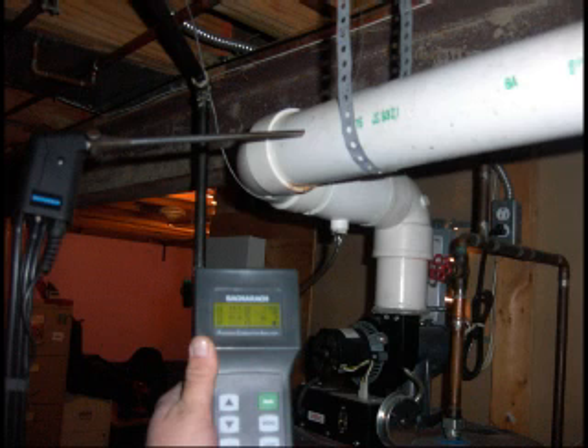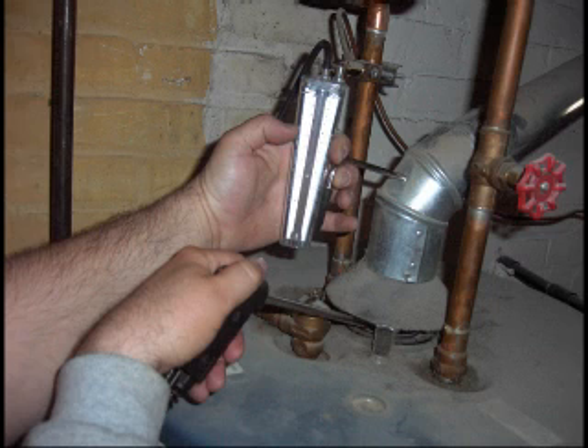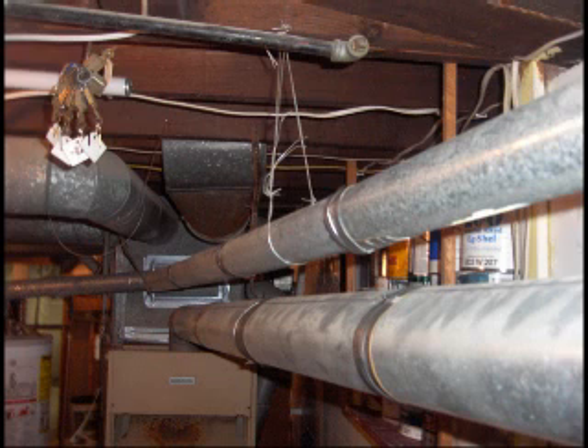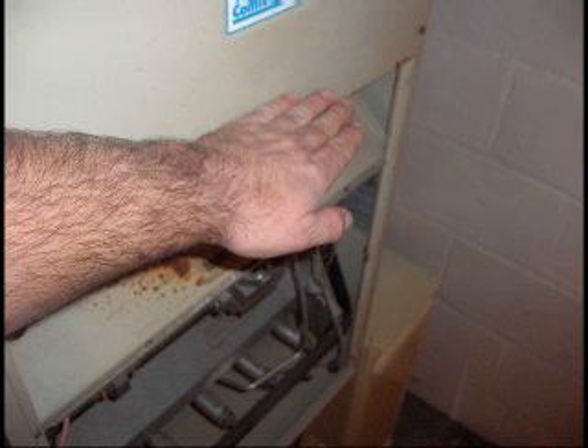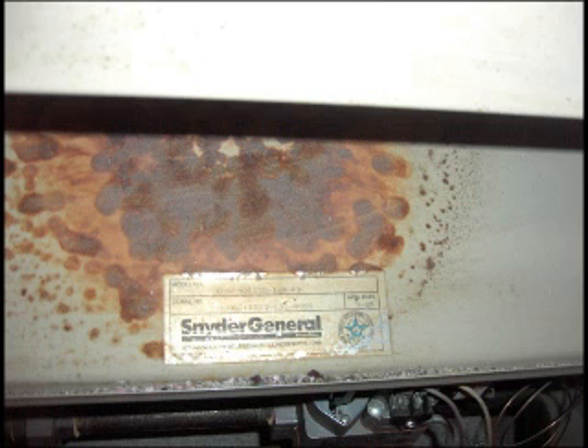You could have a venting problem. You could have a combustion air problem. You could have an alignment problem. You could have a dust or rust problem in the orifices of the burners. You could have a mechanical problem. If they don't check it, they don't know if the fan speed is proper. And if the fan speed is too high or too low, that's going to cause problems with the stack temperatures and potentially create carbon monoxide.